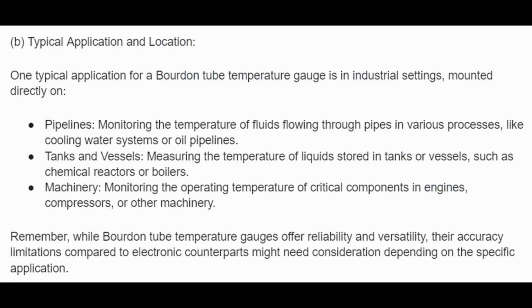B. Typical application and location. One typical application for a Bourdon tube temperature gauge is industrial settings mounted directly on pipelines, monitoring the temperature of fluids flowing through pipes in various processes such as cooling water systems or oil pipelines. Tanks and vessels, measuring the temperatures of liquids stored in tanks or vessels such as chemical reactors or boilers. Machinery, monitoring the operating temperature of critical components in engines, compressors, or other machinery. Remember, while Bourdon tube temperature gauges offer reliability and versatility, their accuracy limitations compared to electronic counterparts might need consideration depending on the specific application.